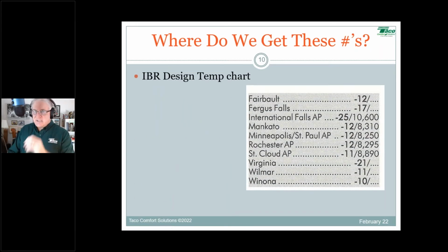Well, in the heat loss handout, we list outdoor design temperatures followed by degree days. Anytime you see a slash with a number, that number after the slash is the estimated degree days for a given area. So in this case, we're looking at Minnesota. There's Faribault, Fergus Falls, International Falls, Minneapolis, St. Paul. There's your minus 12 and 8,250. That's the quote unquote normal degree days for an average year. Some years it's higher, some years it's lower, but that's what they consider average. Those are your average degree days. All right. So you can get rough information there.